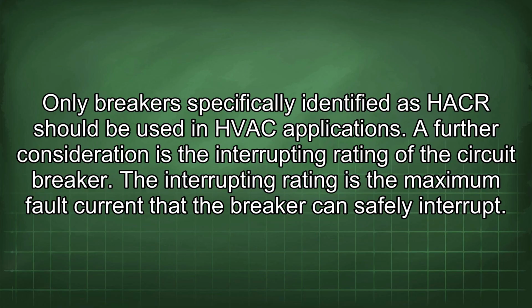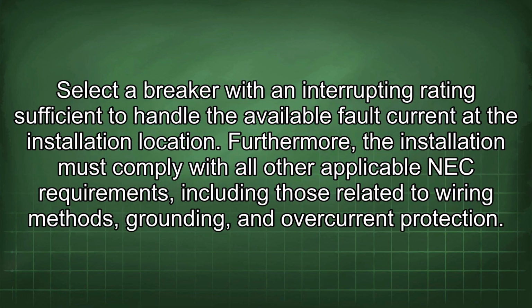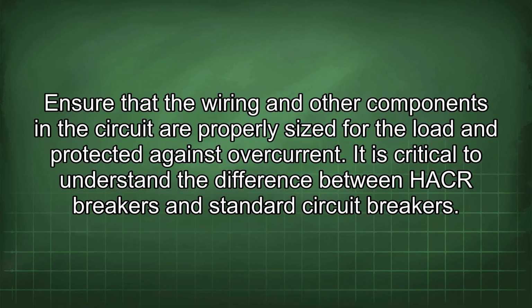A further consideration is the interrupting rating of the circuit breaker. The interrupting rating is the maximum fault current that the breaker can safely interrupt. Select a breaker with an interrupting rating sufficient to handle the available fault current at the installation location. Furthermore, the installation must comply with all other applicable NEC requirements, including those related to wiring methods, grounding, and overcurrent protection. Ensure that the wiring and other components in the circuit are properly sized for the load and protected against overcurrent.